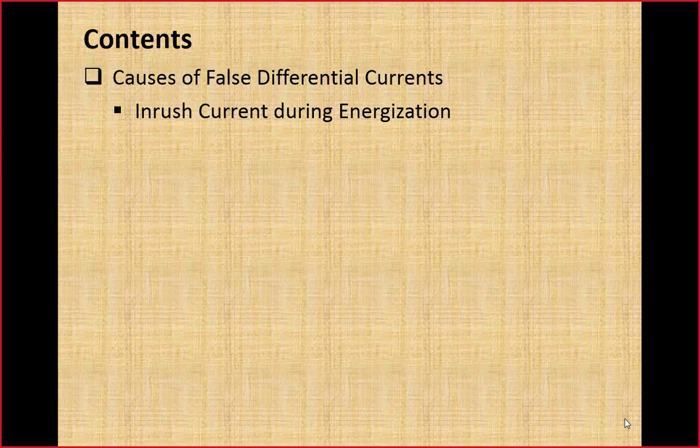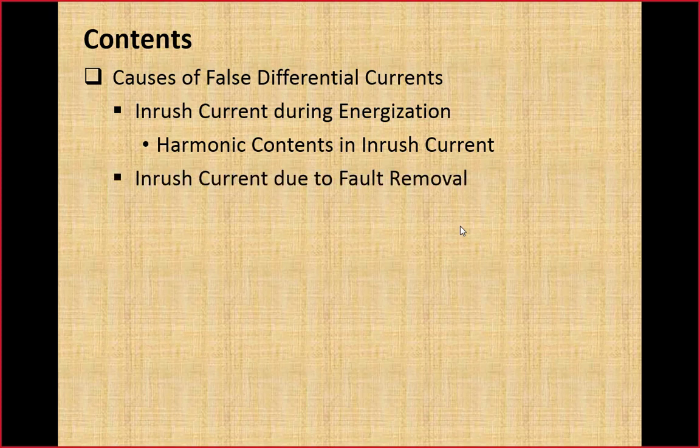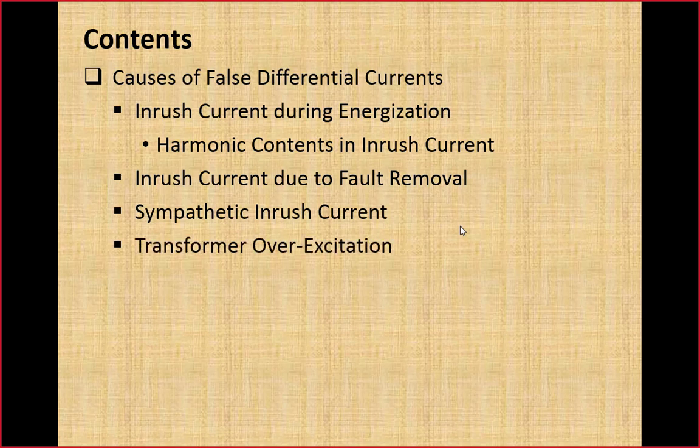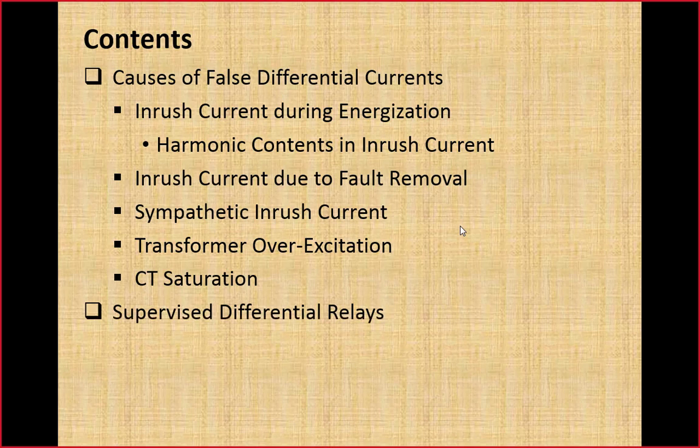First is inrush current during energization. We will also discuss the harmonic content in this inrush current. The second phenomenon, inrush current due to fault removal. Third, sympathetic inrush current. Fourth phenomena is transformer overexcitation. Fifth one is CT saturation. And after discussion of these phenomena, then we discuss supervised differential relay, a method that is used to block the operation of differential relay due to these phenomena.